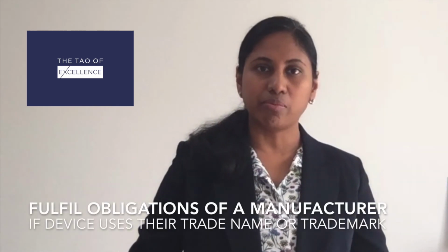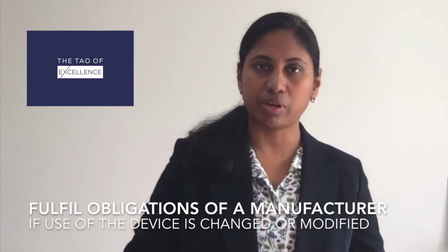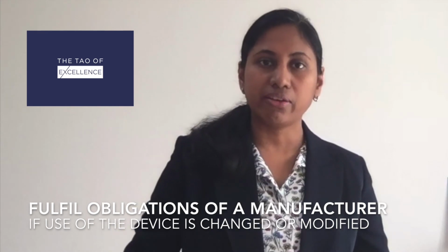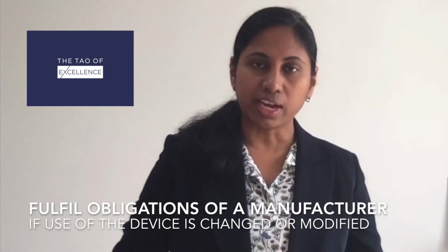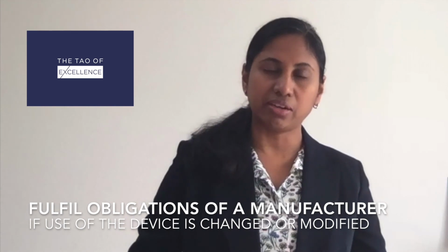The importers might also have to fulfill the obligations of the manufacturers according to Article 16 in the following cases. If the device has been made available on the market under their trade name or registered trademark, if they have changed the intended purpose of the device, or if the device has been modified after it has already been made available on the market. In these cases, the obligations of the manufacturer, which are defined in Article 16, have to be also fulfilled by the importer.